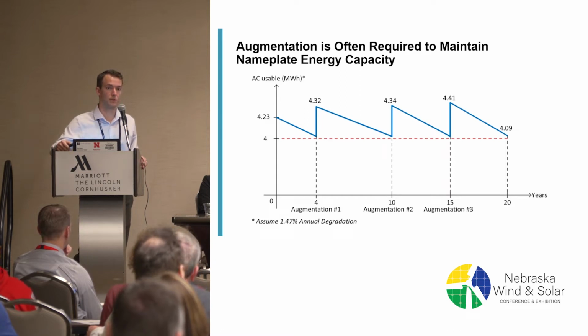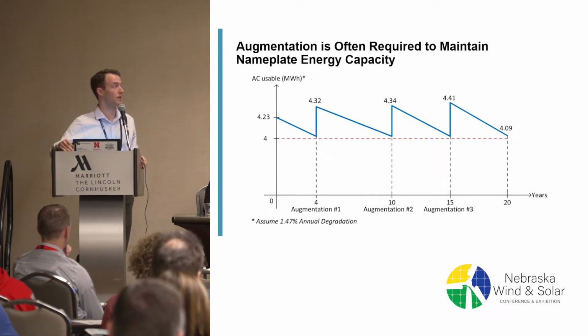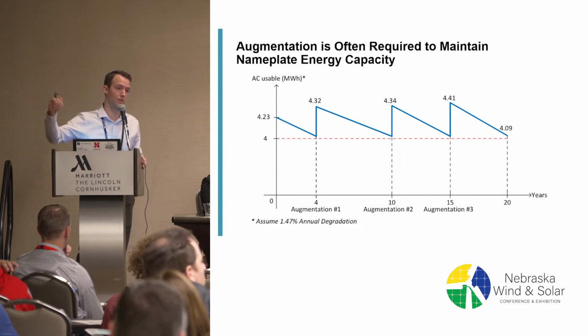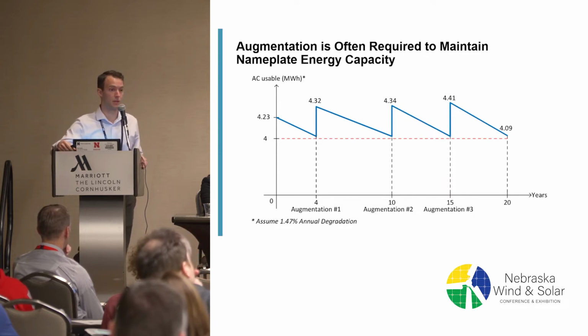One approach is simply oversizing the project when you install it. So in this case, 4 megawatt hours or 400 megawatt hours, you would install maybe 450 or 500 in usable energy, and then ride the degradation curve, monitoring it over time. Periodically throughout the project, you could then augment or add additional battery containers to the system to boost the energy capacity back up, basically playing that curve.